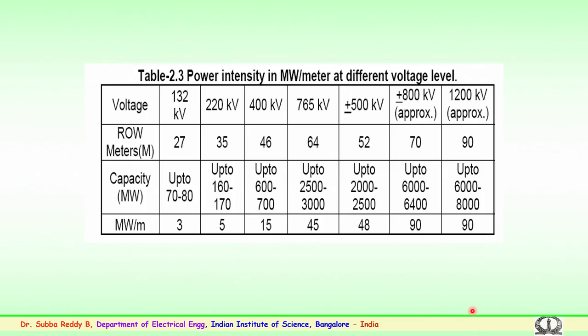As the voltage level increases, the right of way also increases, the tower height also increases, and the capacity to transfer power is also much greater at very high voltages. In the case of a 765 kV system, the minimum right of way required is somewhere around 64 meters, and the power transfer can be 2500 to 3000 megawatts. This is the power which can be transmitted.